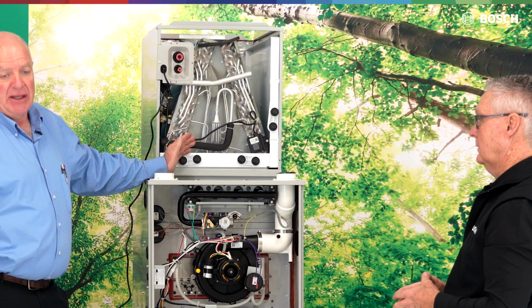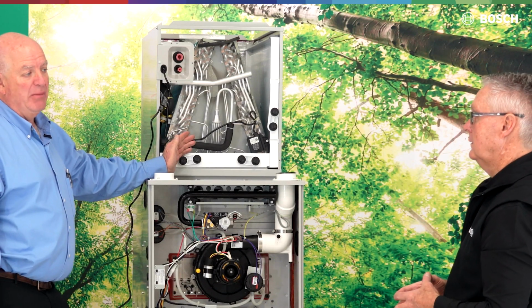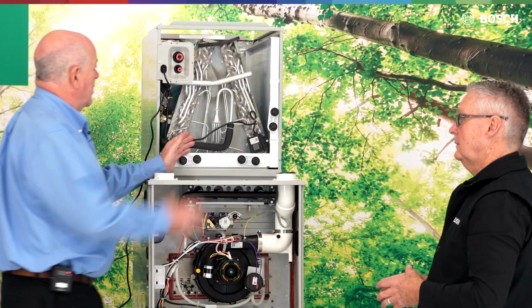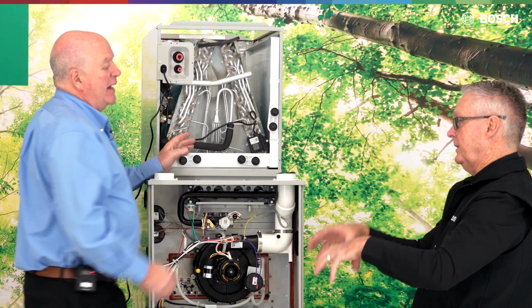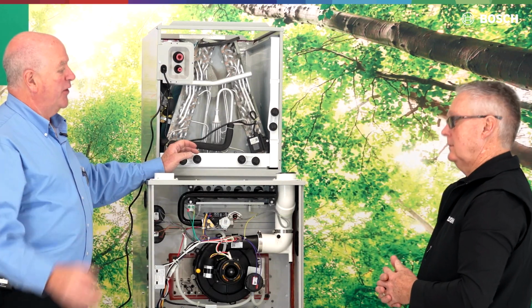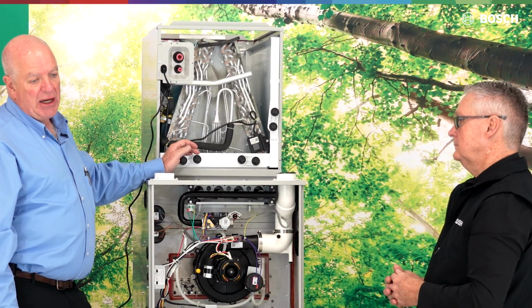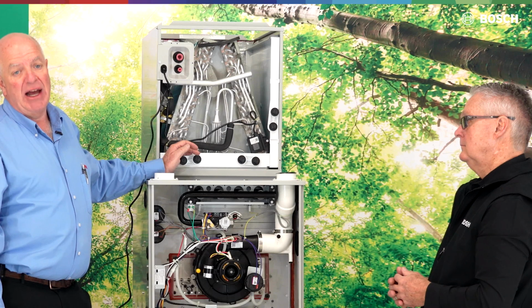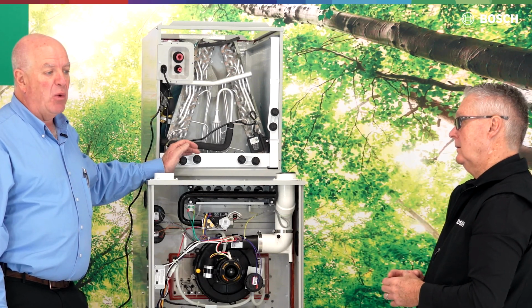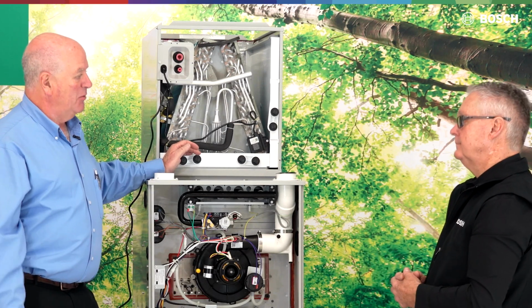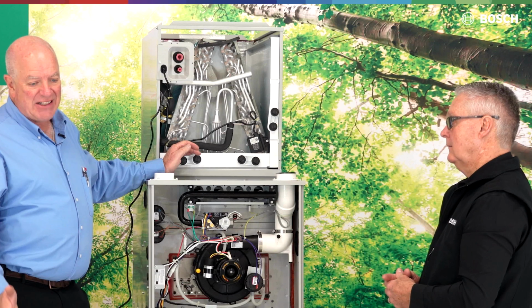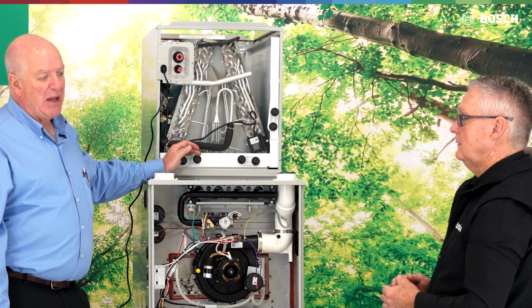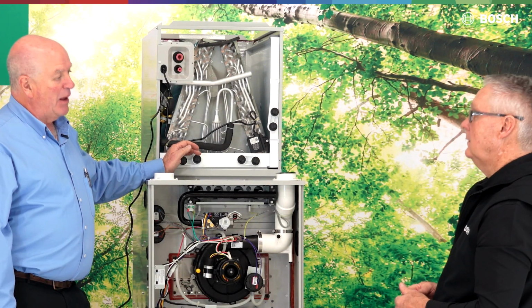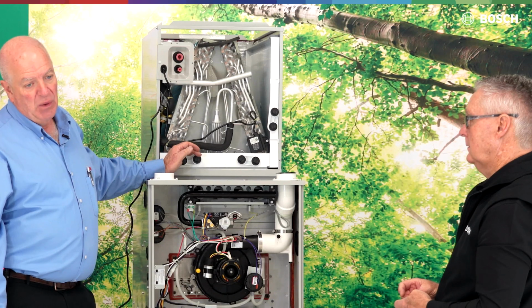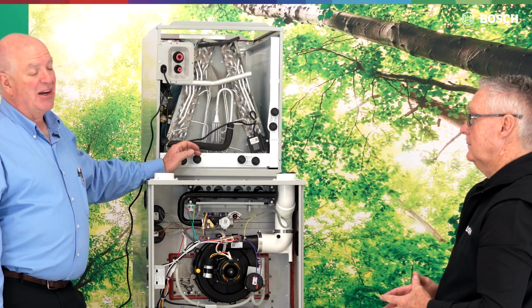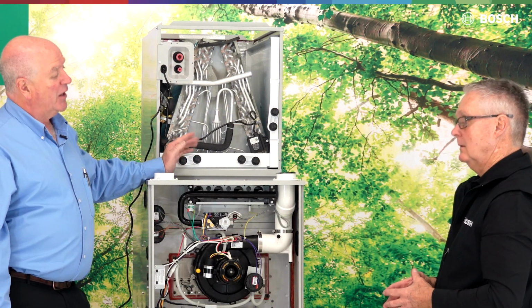These coils do not like UV bulbs. You do not want to put a UV bulb in the air handler where it shines down on that coil, a direct top shot. It'll burn that hydrophilic coating off. Does that mean the coil is junk if the hydrophilic coating goes? It is not junk, but you're going to lose that water-beading capability. Fantastic 409, Simple Green, a garden hose would be the proper items to use. I'd stay away from anything acidic or highly alkaline to clean that coil.